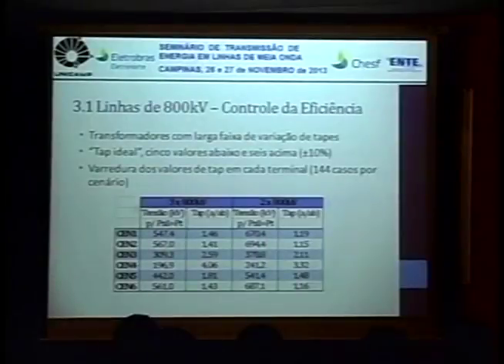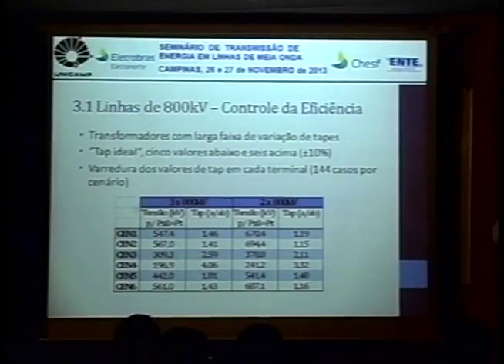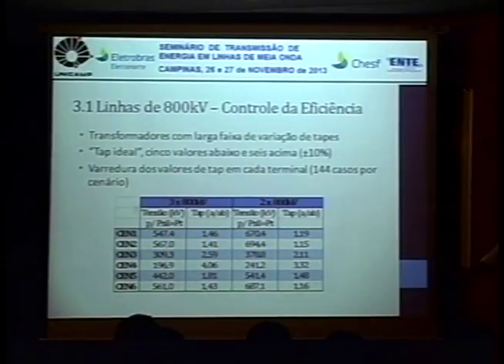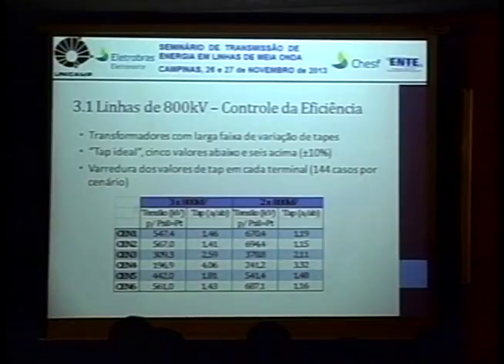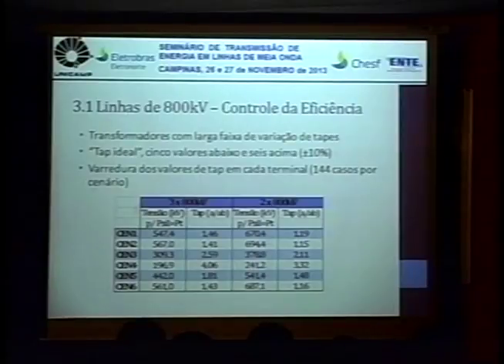So for example, for this scenario, where the load in the half wavelength is very low, I'm going to work with the line at 196 kV. It's not going to reach 800. In some cases, it's going to operate with 560 kV. So I need to adjust the tap at this position. This is the ideal tap position, to guarantee that the transmitted power is similar to, or exactly the same as, the characteristic power.